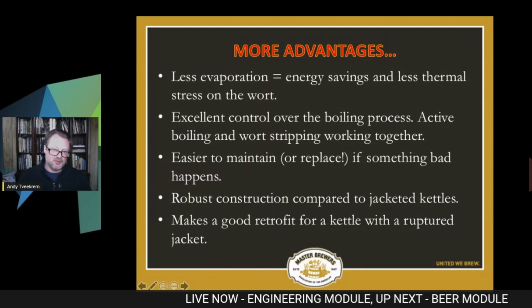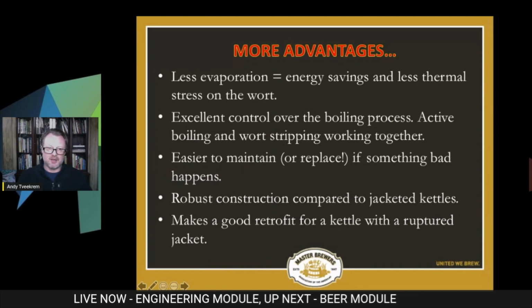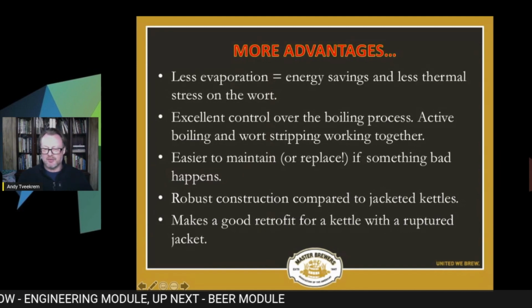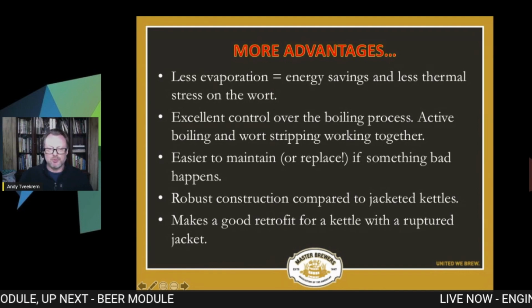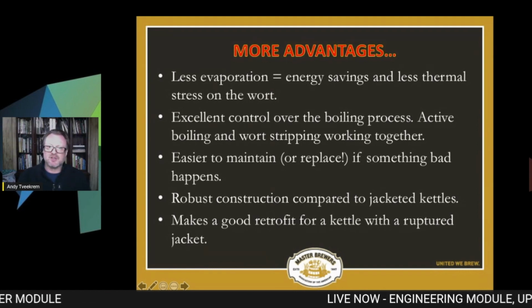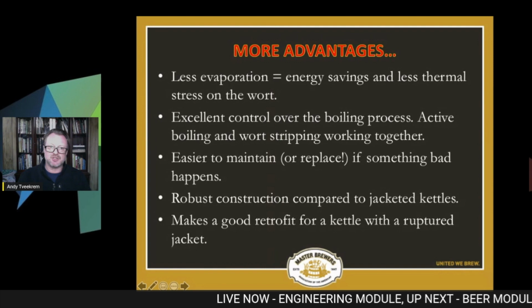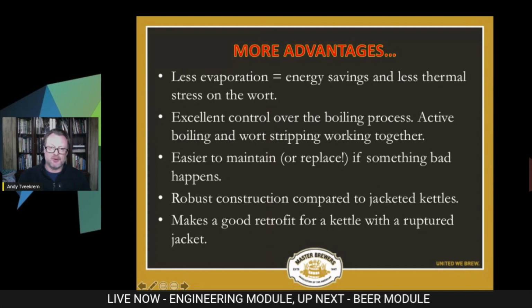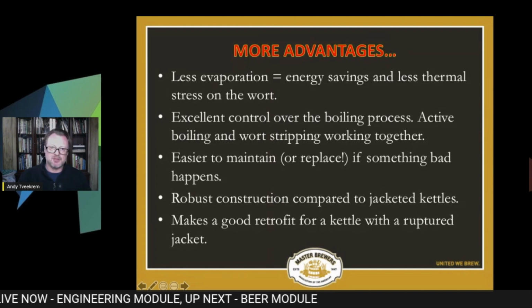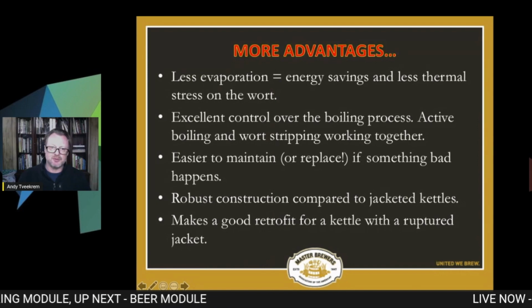And especially if you have an internal boiler and say, I don't know, something goes wrong, you have a corrosion problem and you need to just remove the whole thing, that thing's coming out in pieces. It's not just, put a strap around it and hoist it through the roof. It's a much harder job to replace an internal calandria.